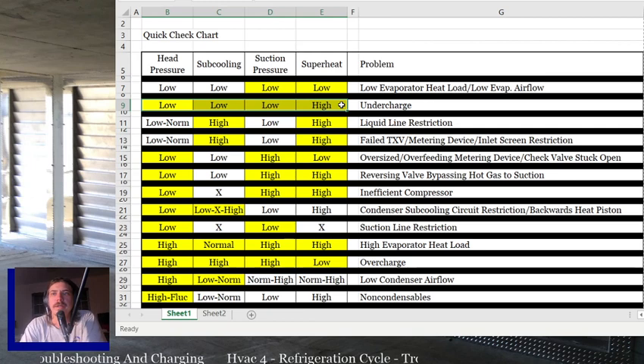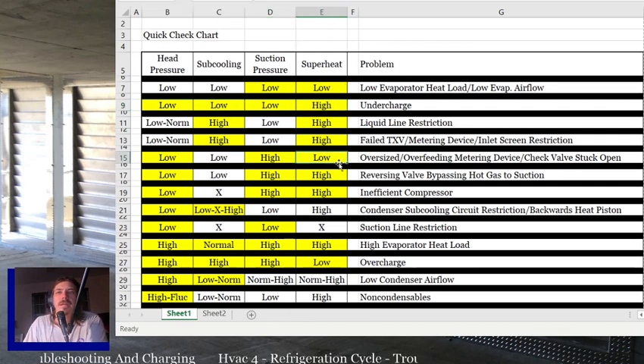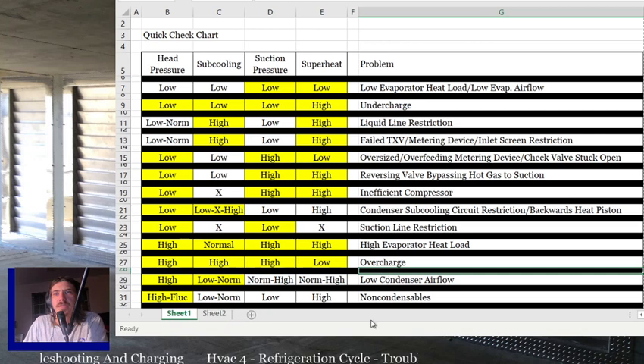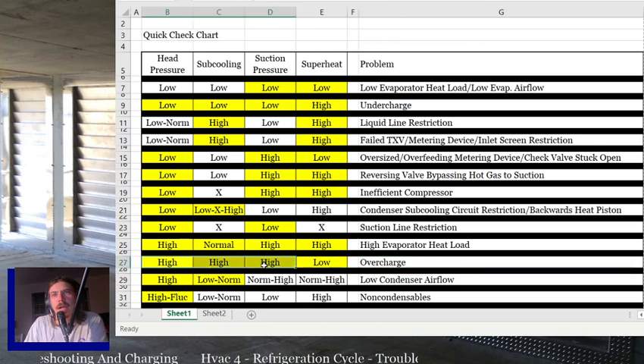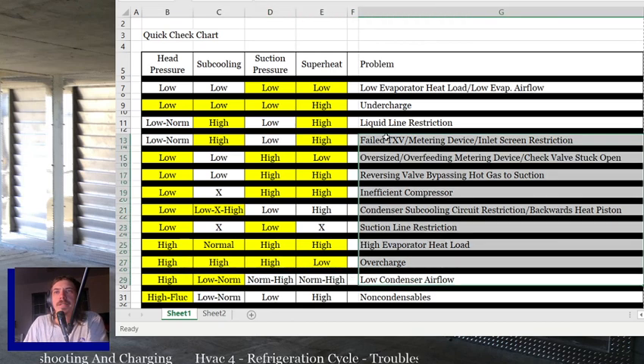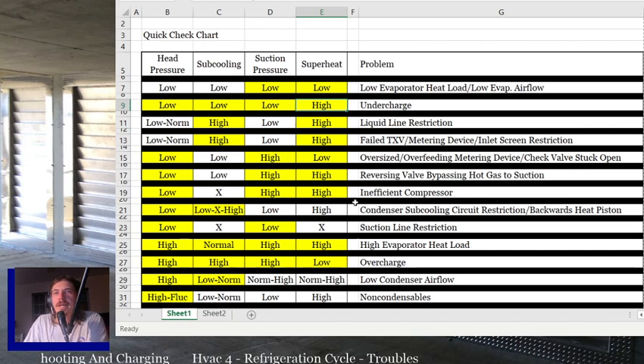So it's just a way to pick it out a little bit quicker, and you know what values are most important to be looking at if you suspect. If I suspect the filter's really dirty and that's the problem with the system, then I'll look for low suction pressure and low superheat. If I suspect that an overcharge is the problem with the system, then I'm going to look for everything to be high except for my superheat, which will be low. Things like that. So that's what the highlighting is there for. Did I ramble on too much, or does that make sense?